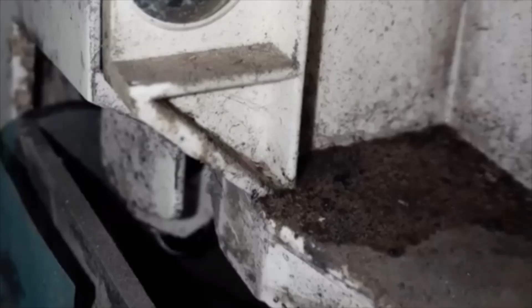Next reason may be a damaged condensate tray. The condensate tray of the air conditioner collects the condensed water. If, however, the tray is broken, rusted or damaged, the water will seep through it and leak into the room when the air conditioner is running.